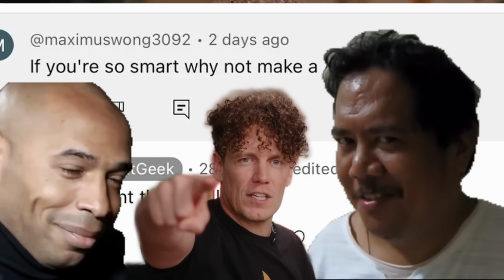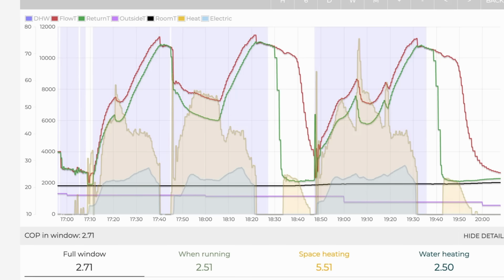That's everything we set out to do, and it all came together in what we're now calling the Nano Store. Take that, Maximus Wong 3092. Looking at the data, we'd hit a SCOP of around 2.7, and that was around 18 degrees outside, so 3 times more efficient than a gas combi boiler, despite hitting around 60 to 75 degree flow temperatures. Simon's actually done a whole video on this, so go and check that out.